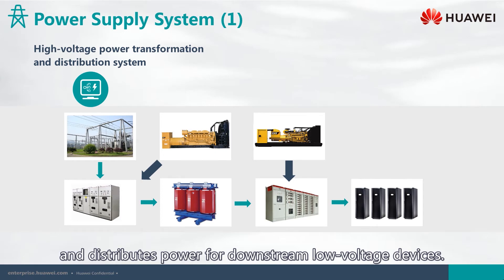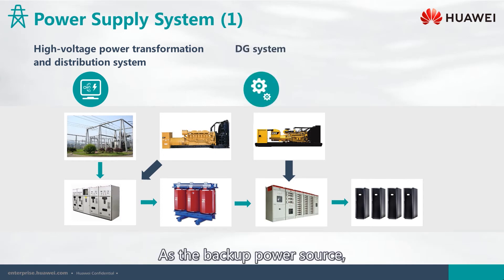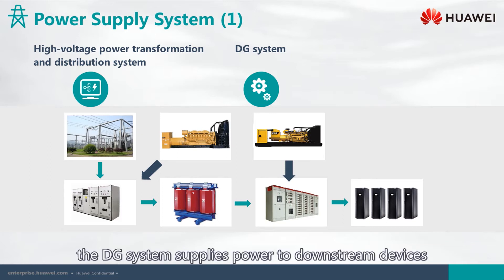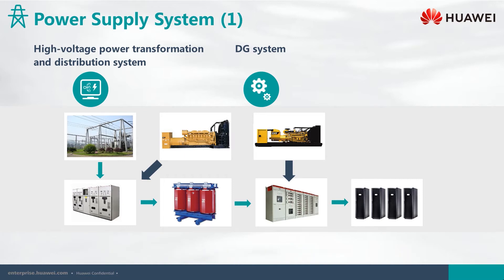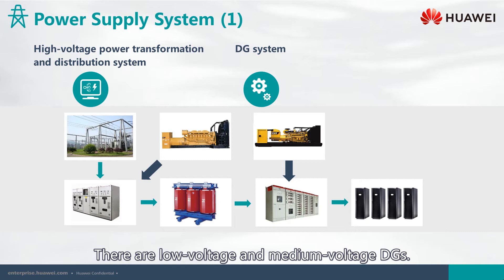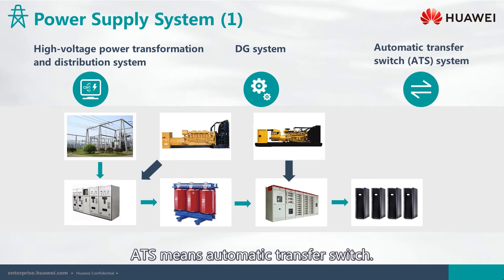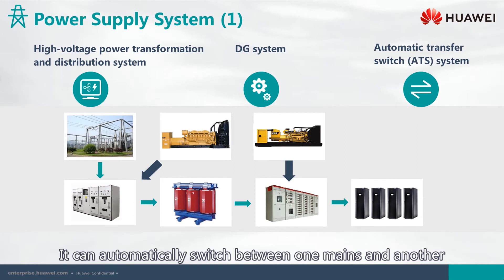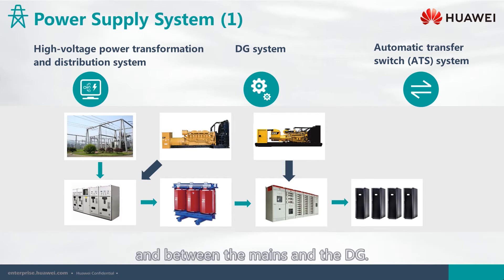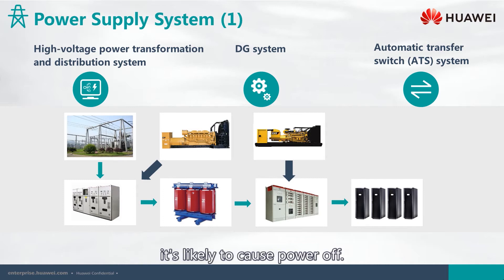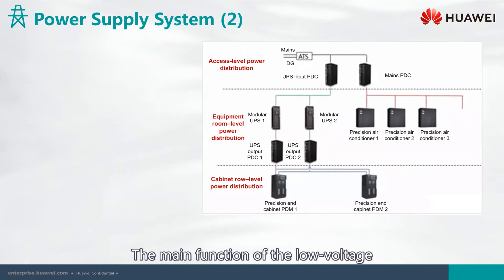The DG system serves as the backup power source, supplying power to downstream devices when the mains power fails. There are low voltage and medium voltage DGs. ATS means automatic transfer switch — it can automatically switch between one mains and another, and between the mains and the DG. It is a mechanical action with a transformation time of more than 100 milliseconds, which is likely to cause a power outage.